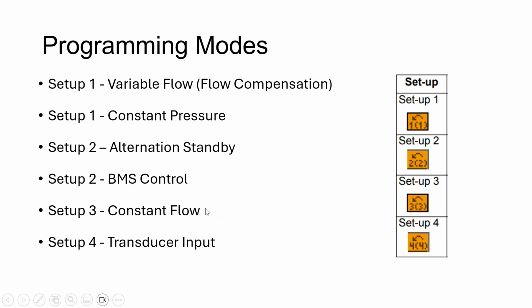If you think about it, if you've got a primary chiller that needs 1,000 GPM, you set the drive and you're going to get 1,000 GPM on a consistent basis. That chiller is going to be very happy. If you've ever sat through one of Rich's classes, that chiller is going to have the smiley face when he's doing his primary, secondary discussion. And then setup 4 is where you can override all of the other ones and accept the outside signal.